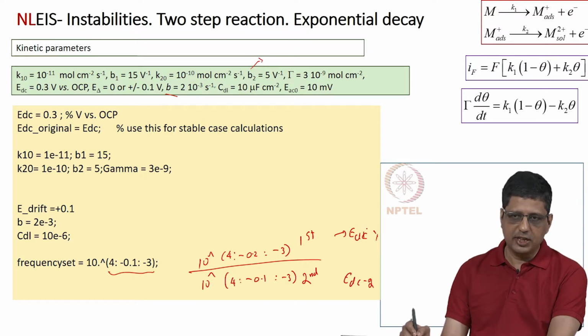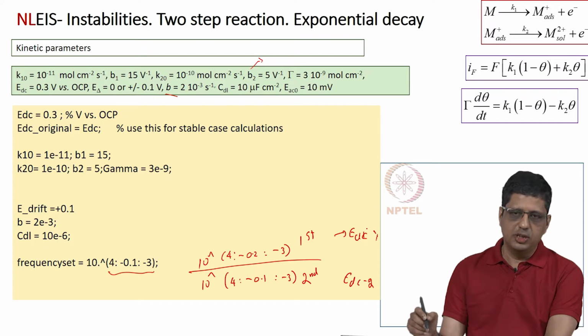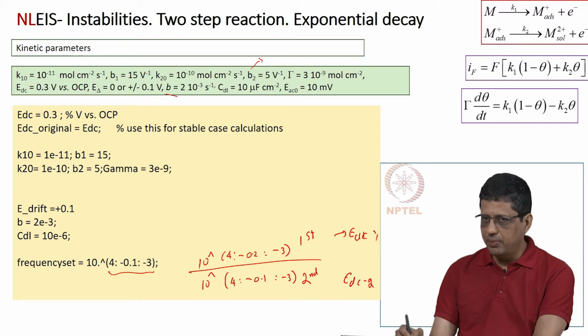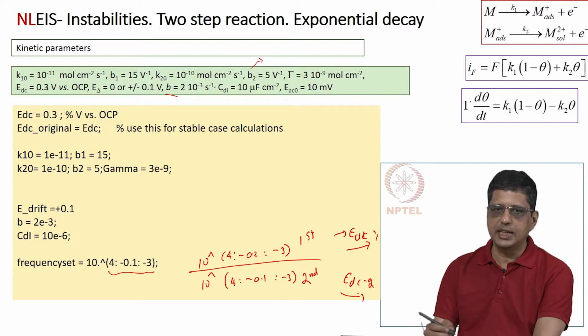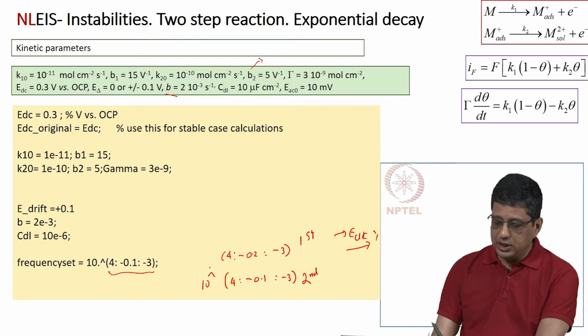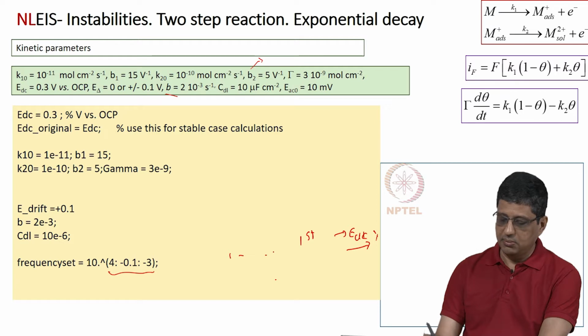When the open circuit potential changes with time, with respect to OCP the DC values will be different at the end of this experiment and different at the end of the second set of experiments. So, it is not just how fast it drifts, it is also how long we take to make the measurements that plays a role in how the spectrum will appear.